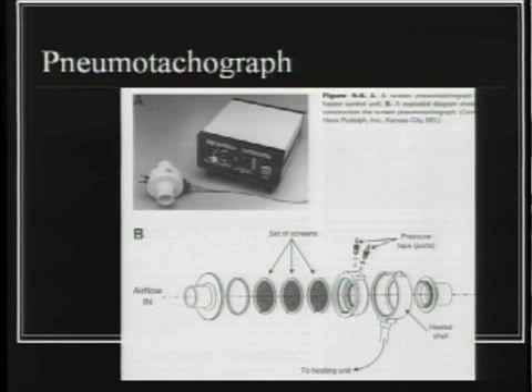Now you'll see in the video we're going to watch, the device that's used to calibrate a pneumotachograph is a real pain to do. It's a glass tube with a little ball that floats in it, and you connect it to compressed air. You turn on the compressed air canister, hope it's not going to shoot all over the place, and you adjust it so the little ball is floating in this glass cylinder at like 100 cc's per second or 200 cc's per second. It's really a pain to calibrate. And you'll see that in just a minute. That device is called a rotometer. R-O-T-O-M-E-T-E-R. A rotometer. So the rotometer is what's used to calibrate a pneumotachograph.